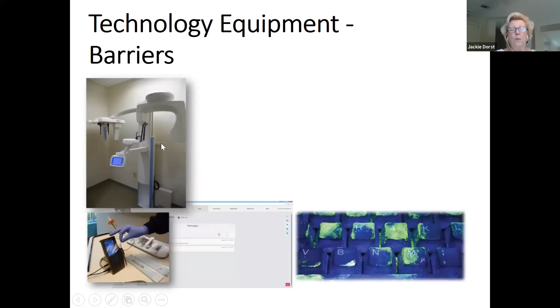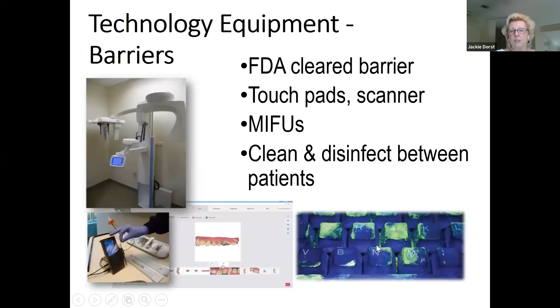For technology equipment, because it can be sensitive to liquids or aerosols, you want to have the manufacturer's instructions for use. Always use an FDA cleared barrier. And some disinfectants, if they have high alcohol content in them, might inactivate the touchpad screen. Have the manufacturer's instructions for use, and then clean and disinfect in between each patient. Keyboards that are in the clinical area are one of the common sources of cross-contamination because we enter patients' information with our gloves on. So using a barrier over them is an option.